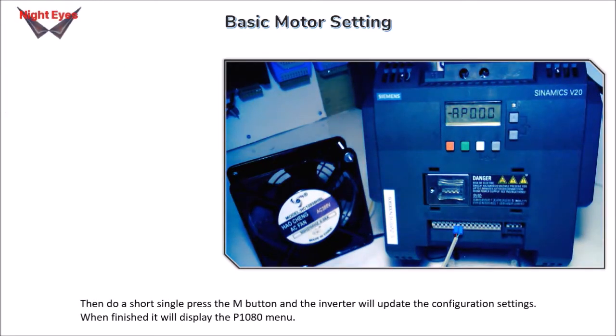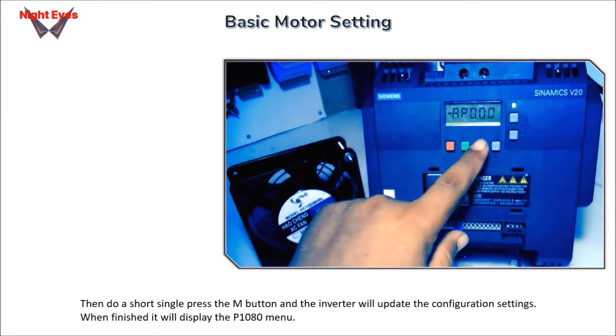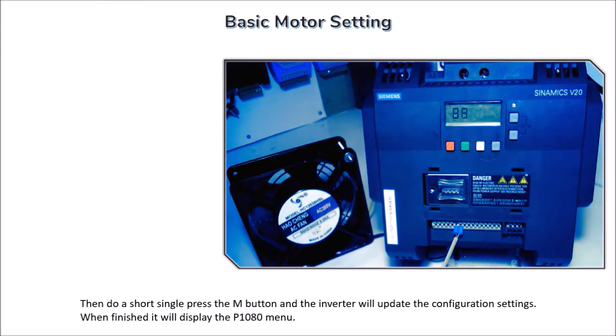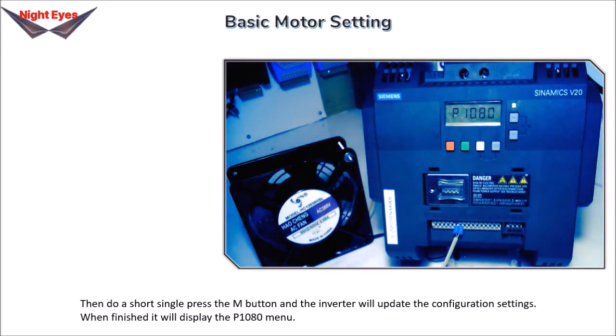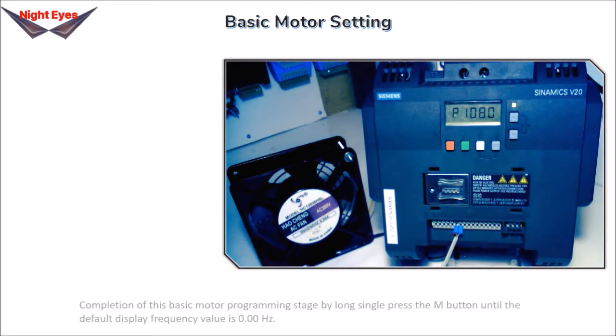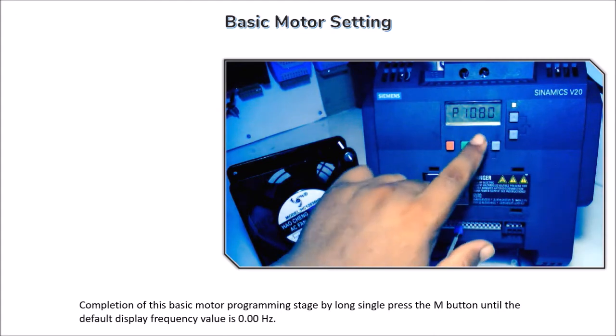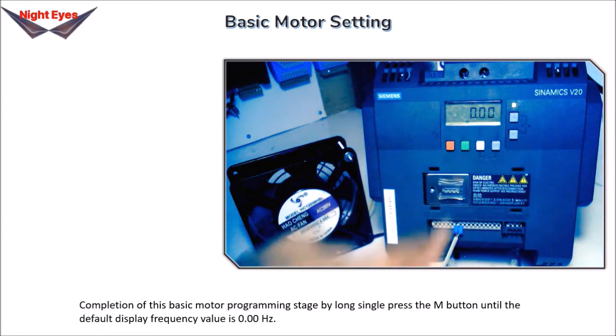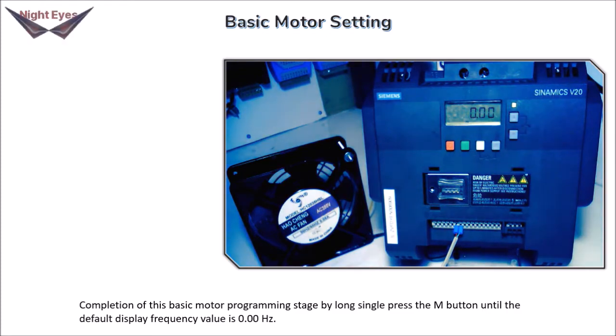Then do a short single press of the M button and the inverter will update the configuration settings. When finished it will display the P1080 menu. Complete this basic motor programming stage by long pressing the M button until the default display shows a frequency value of 0.00 Hz.